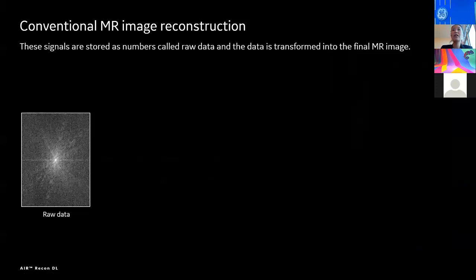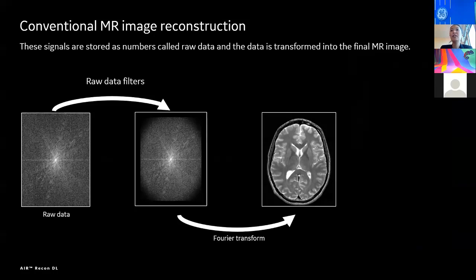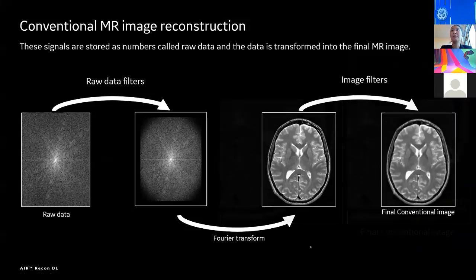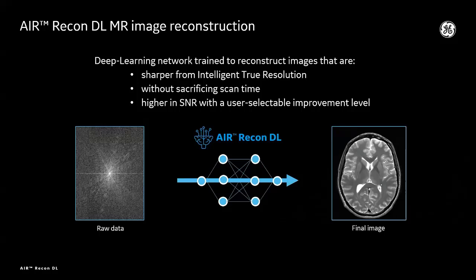In the conventional way, when you try to scan faster, we need to under-sample data. In that case, because we don't have enough raw data, image quality is degraded. To make it up, we apply a filter after MR images are reconstructed. But those image filters are not perfect. That's why images get blurry and some artifacts are still remaining on the images. AIR Recon DL's approach is totally different. Deep learning based technology is integrated into the reconstruction pipeline, operating on MR raw data — not reconstructed images — to address this problem.